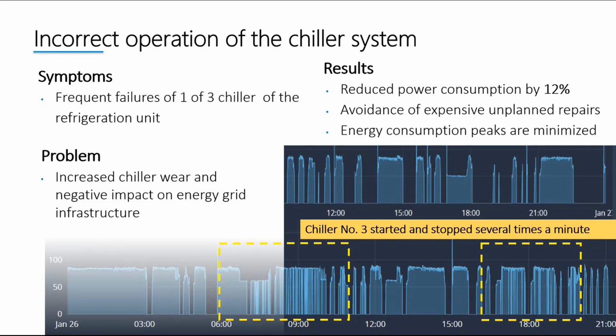The interesting thing is, with their existing SCADA solution, they could not identify the problem because SCADA only showed that the temperature was fine, minus 18 degrees, no problem, but it didn't really show how the chillers behave and their energy consumption and mode of operation at that time. So we implemented the platform quickly, in 2 days, and after a certain period we realized that while the first and second chillers were running as they should, the third chiller, shown in the diagram here, was running in a very inefficient and unhealthy mode.